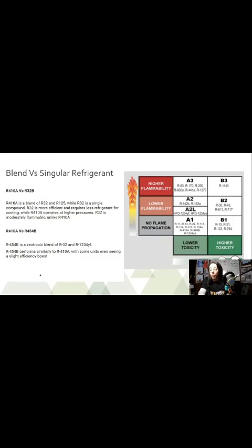R410A versus R454B. So again, R32 is half of 410A. R454B is a zeotropic blend of R32 and R1234yf. R454B performs similarly to 410A, with some units even seeing a slight efficiency boost. So R454B will behave like 410A. We'll see similar pressures, similar temperatures, things like that, but we will have way more efficiency in these newer units. And that's why we're going to a lot of VRF, because those are even more efficient.